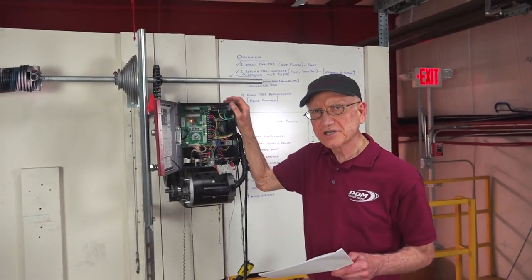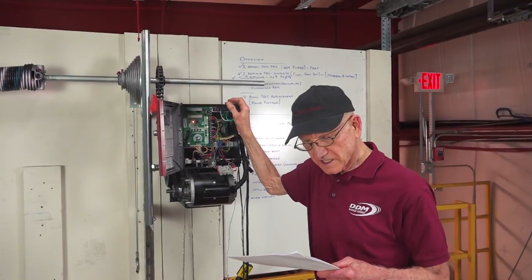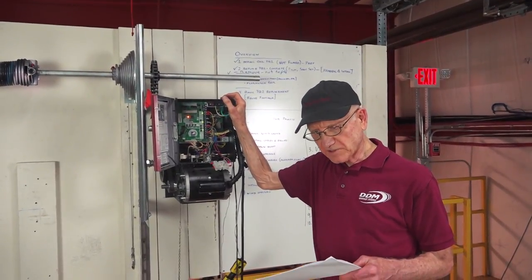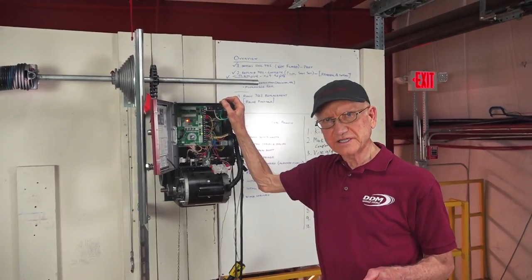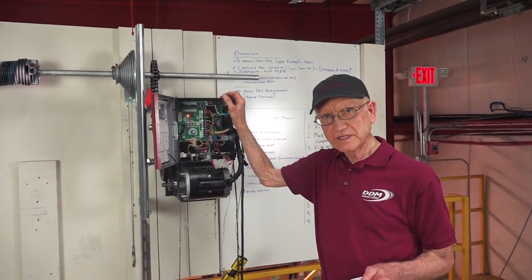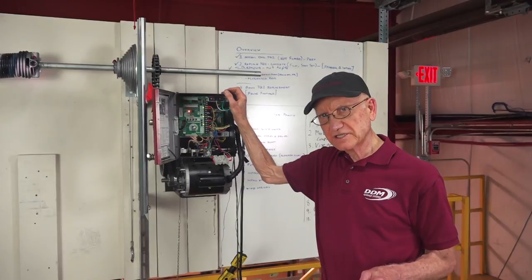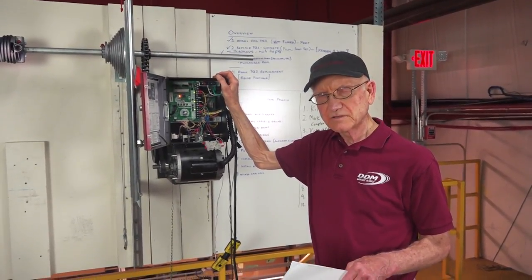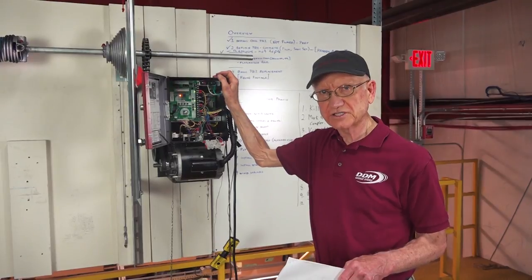Another error code that you may get is with eight blinks. This would indicate that there's a brownout detected. If you're ever getting eight blinks, you need to check your voltages. We have a separate video where we show how to check the voltages.